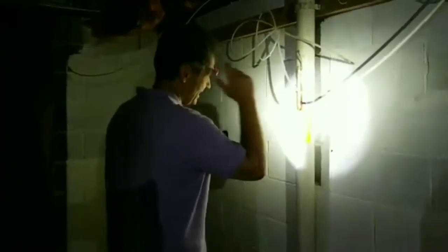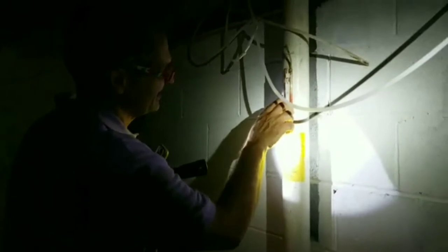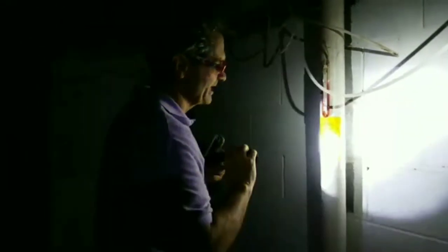So that's what that is? And is there any way to know if it's working properly? Yes — this is a manometer. It doesn't look like it's working properly; there's paper in the top of the pipe outside. One side of this should be much higher than the other side, which tells you there's negative pressure. It's doing the same thing as the fan in your kitchen that sucks all the air out — it's creating negative pressure underneath the slab, taking whatever gas is underneath and getting rid of it.